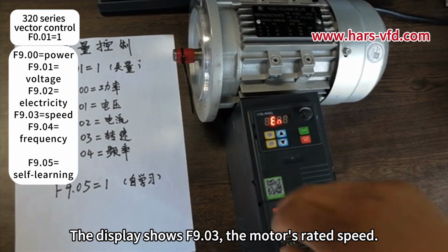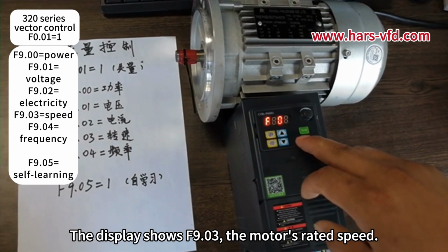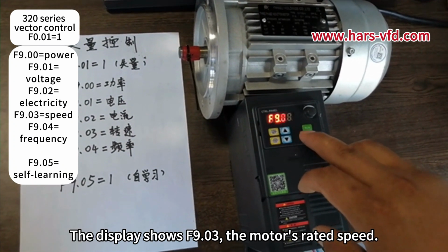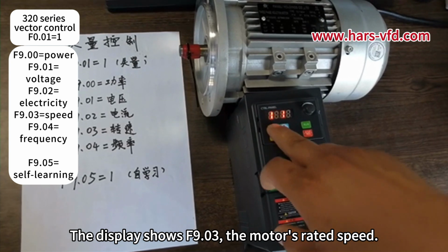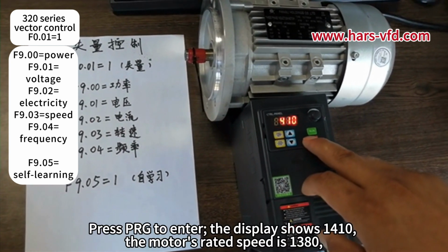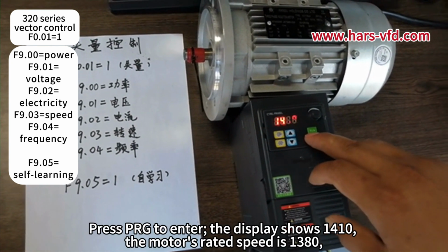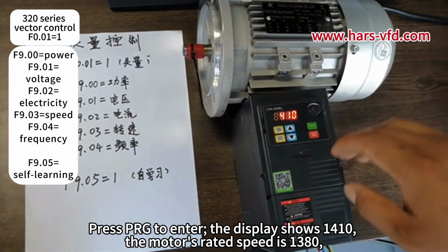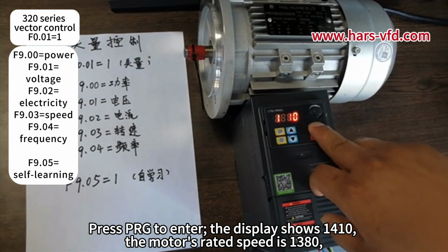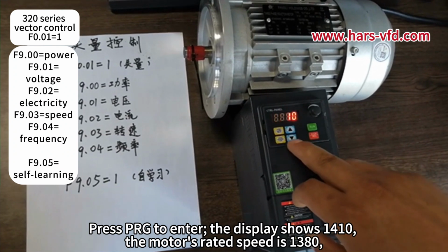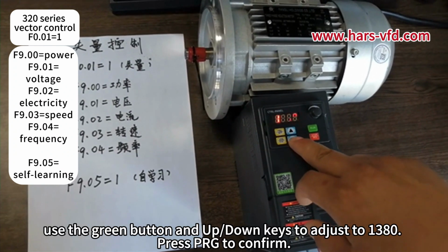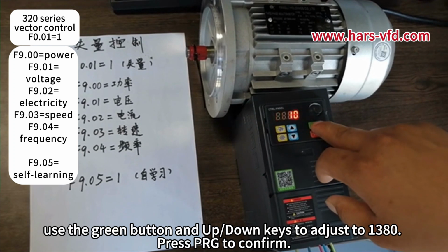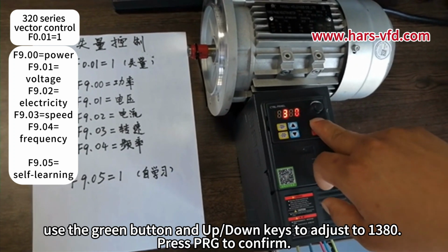The display shows F9.03, the motor's rated speed. Press PRG to enter. The display shows 1410. The motor's rated speed is 1380. Use the green button and up or down keys to adjust to 1380. Press PRG to confirm.